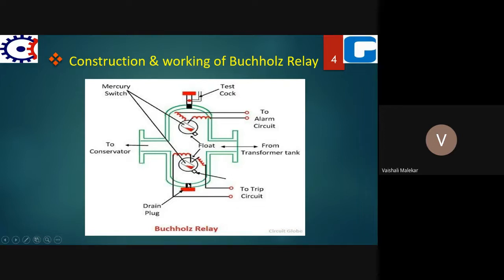So you can see here the oil filled chamber and two hinge floats. One is on the top side, the other is on the lower side. At the top side, the hinge float is accompanied with a mercury switch, and the mercury switch is connected with the alarm circuit. At the lower side, the hinge float is again accompanied with a mercury switch, and the mercury switch is connected to the trip circuit.